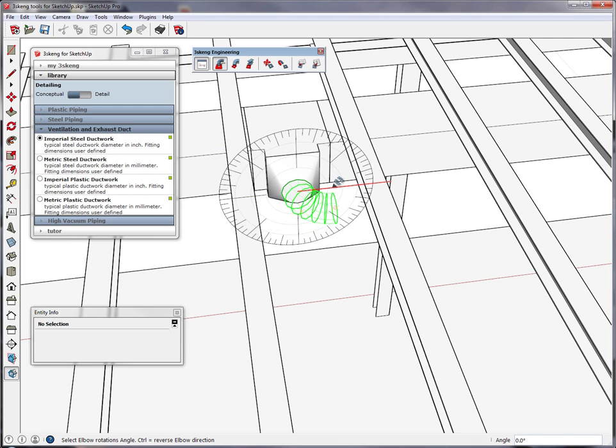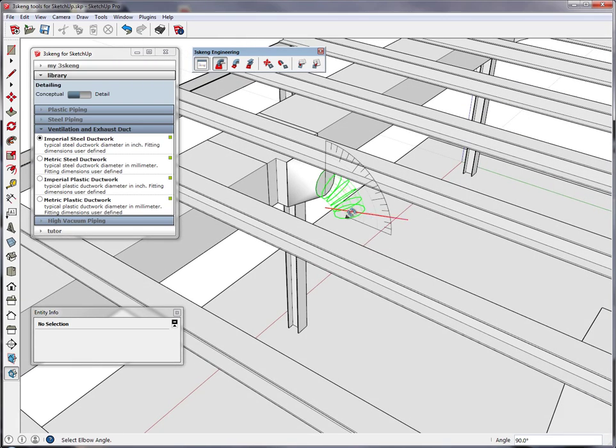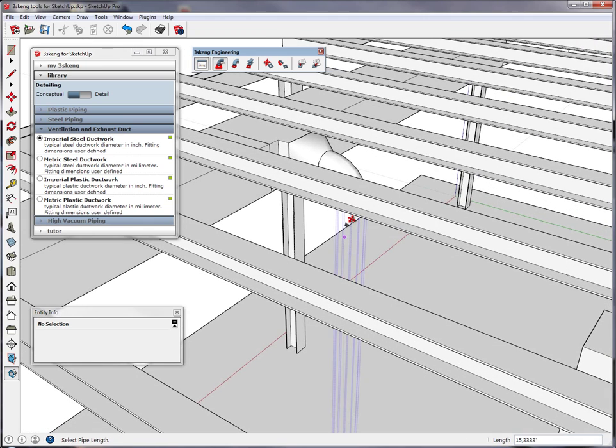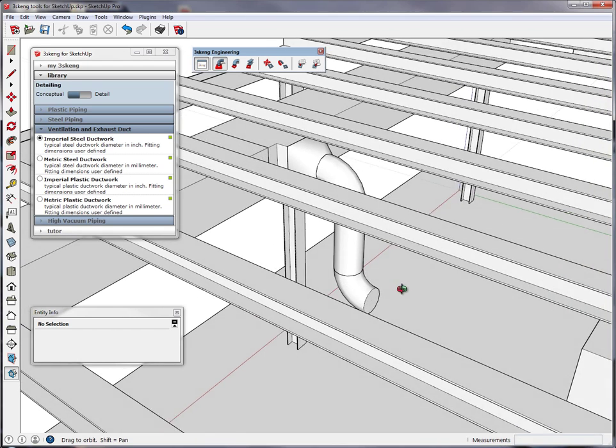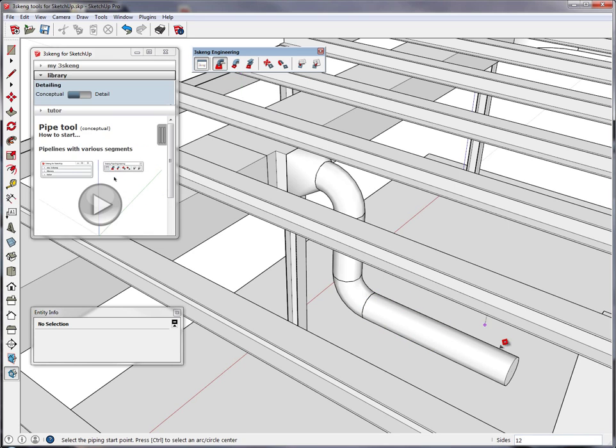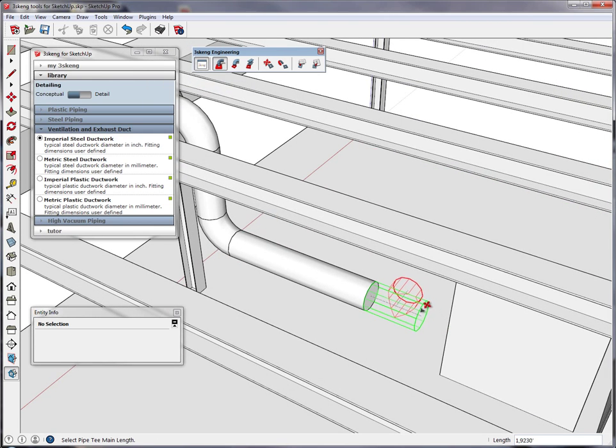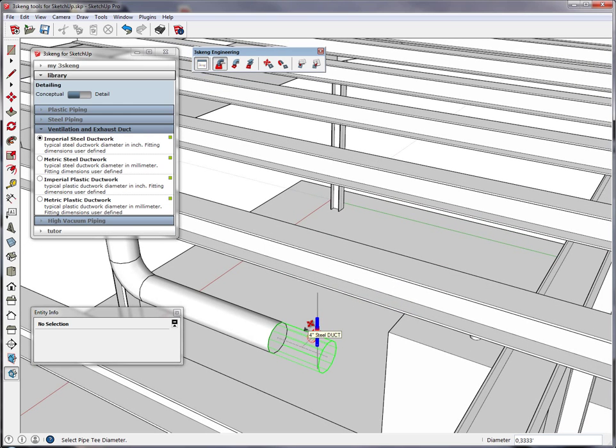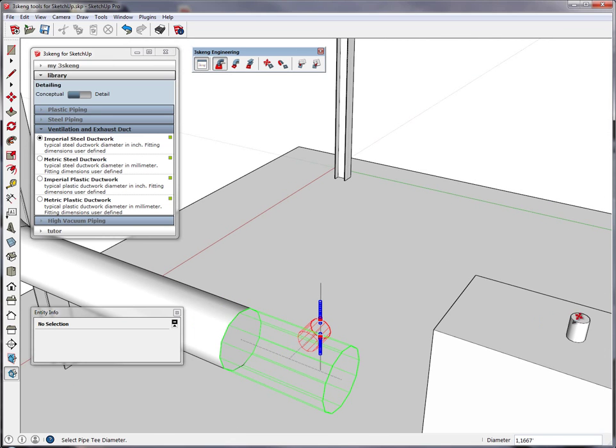Selection again shows you where you want to have the elbow facing. We use face downward 90 degrees and a radius to diameter ratio of 1. We attach a straight piece indicating 3 feet, add another elbow facing on that side, double-clicking to confirm the parameters, then make a straight piece of 6 feet. We add a T-piece which is supposed to be 2 feet long, facing towards our fume hoods. Now we have to select the size or dimension of the outlet — we hover over the fume hood and it will immediately catch the pipe outside diameter of this component and pre-select it in our T-outlet.